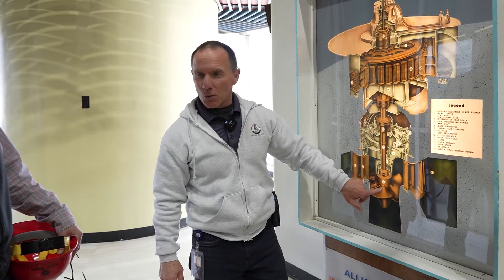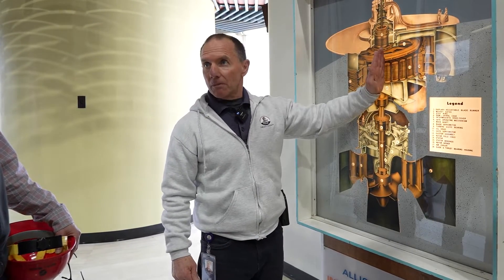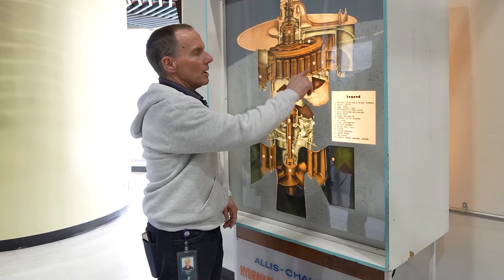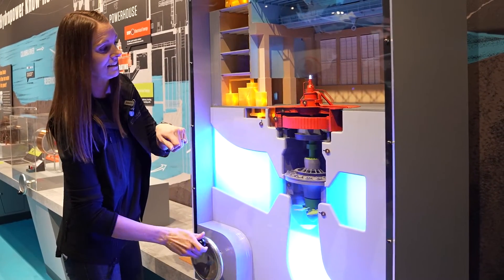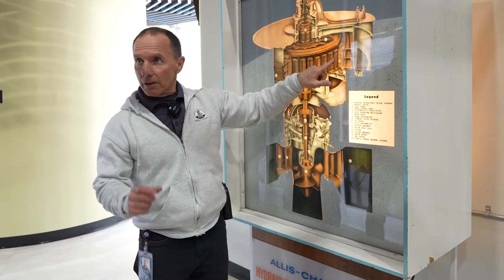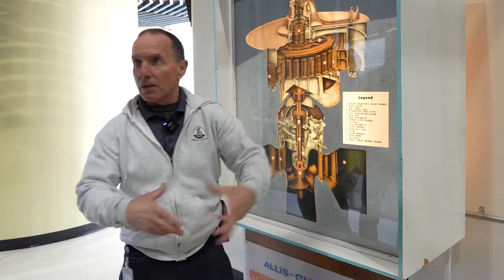The combined weight of the turbine — about 400,000 pounds — plus the shaft and a 426-ton rotor: when the water hits the blades, it's going to fractionally lift and spin. Everything that's spinning is about two and a half million pounds. The rotor — think of it as alternating north pole, south pole magnets all the way around — is surrounded by a stator, which is coiled copper. You've got 8 million gallons of water a minute spinning two and a half million pounds at 90 RPMs. The surface speed of the rotor is about 125 miles an hour. The tolerance between the rotor and the stator — your coiled copper — is about three-eighths of an inch. That's your air gap, where you're generating your electromagnetic current. That's your electricity.